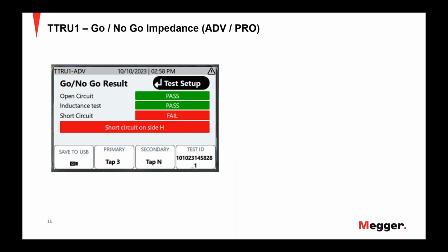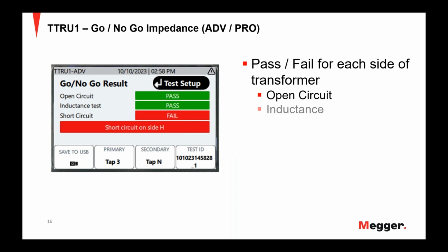And then a quick look at the go, no go impedance. The main point to make here is that, again, we are going to show you the exact place where this failure happens. And on this particular test, on a single phase transformer we had in the factory, what I did was I put a short across the secondary, or across the primary. And we see here that it is reporting that the short circuit was on the H side. So again, go no go is a great way to pinpoint issues if you see your turn ratio results aren't as expected.